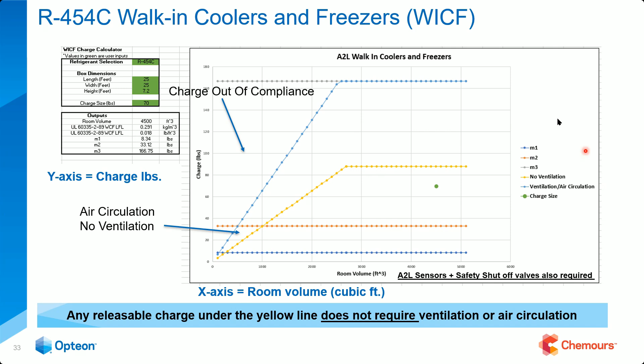Now, this triangle area here needs air circulation, but no ventilation. So this is way down here with a small charge, but a very small area. So inside this triangle area, we're going to turn the evaporator fans on and move some air, but we wouldn't need ventilation, either removing or bringing in. All right. So that's the second one. So let's look at it a little further here. And the reason we're moving that air, as I said earlier, is in case there's a leak, you would move that concentration and lessen it.